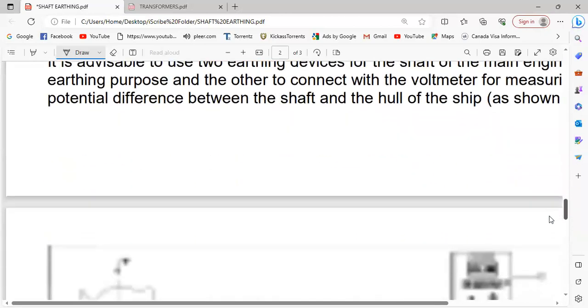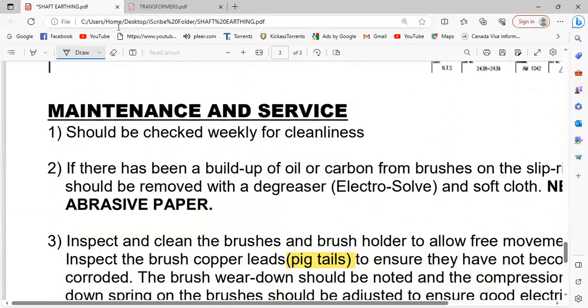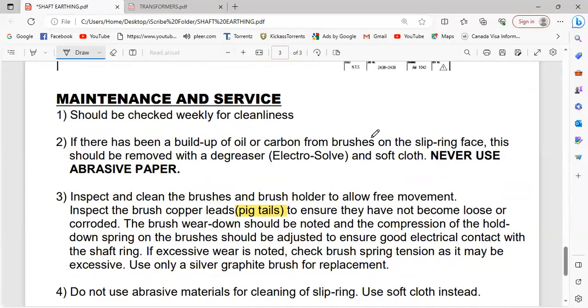With regard to the pigtails, those things can sometimes get eroded and become very thin, and thus those few strands will not be giving you a proper conductive path for your earthing current to go down to ground. So see that they are also in good condition. If not, replace them. Your brush may not have worn down, but this can also cause spark erosion or pitting in your main engine bearings. Such a simple reason. The brush wear down should be noted, and the compression of the hold down spring of the brushes should be adjusted to ensure good electrical contact with the shaft ring. If excessive wear is noted, check the brush spring tension, as it may be excessive.